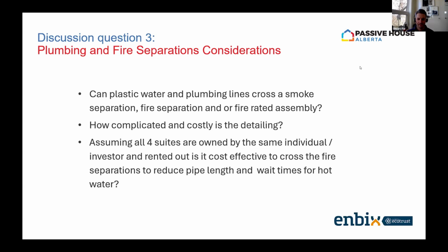I agree. At the scale of 4 suites, I might price out both. It might be a question of floor area too. The decentralized approach might be a package air source heat pump tank, like the Rheem or A.O. Smith type unit. They're very cost effective, plug and play, if you have space for them. They make a bit of noise though, so that's a consideration. Four of those might run about $12,000. But at 4 suites and plus, you start getting into a range where centralized technology makes sense, taking the load off the space heating system. Those package units are just sucking heat out of the space, so you have to figure out your compounding COPs to determine overall efficiencies. At the scale of 4+ units, I think central starts to make sense, but I'd price it and consider those other factors—space and noise.